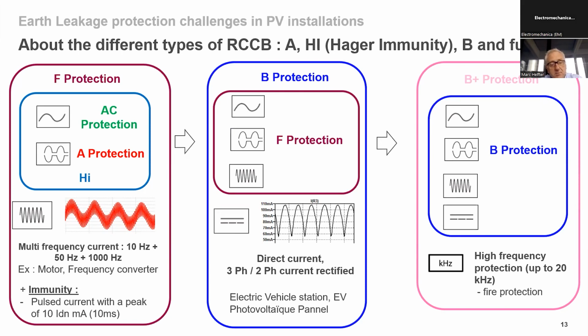This protection type is specially intended for converters and power electronics. So you will be able also to detect currents occurring at a frequency of 10 hertz, 50 hertz, which is standard grid frequency, and 1000 hertz. And this product will combine these three frequencies to provide a better level of security. These products are not available today. They are in development, and I guess they will be available in the market within, let's say, 2-3 years.